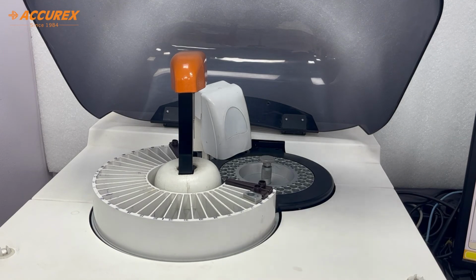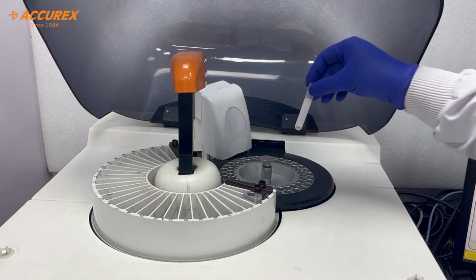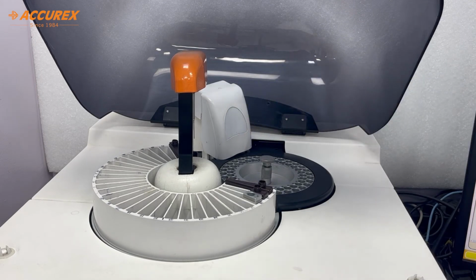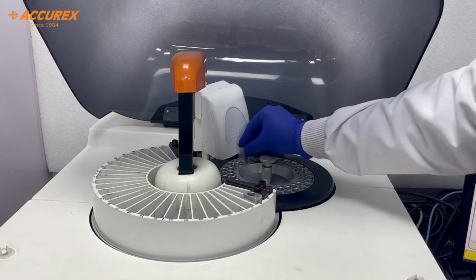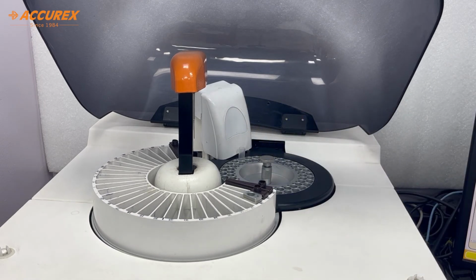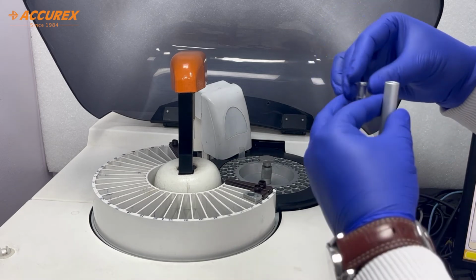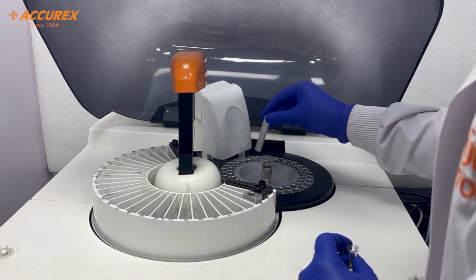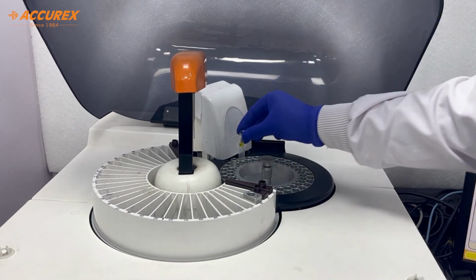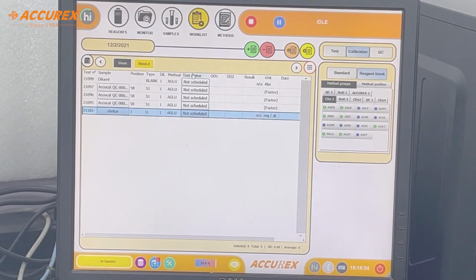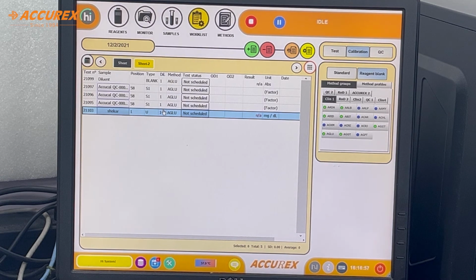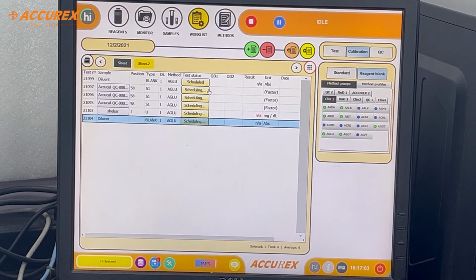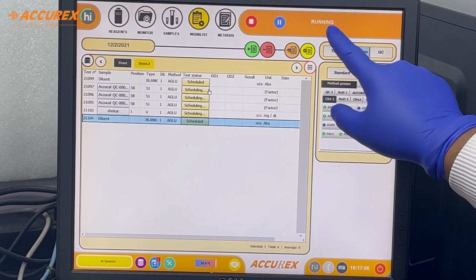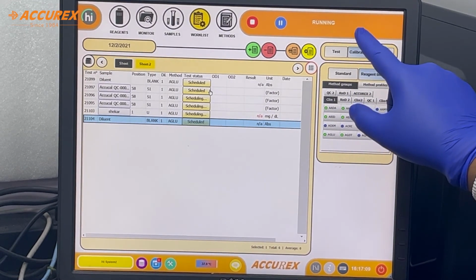Now open the instrument cover. Now you can place the tube where the position has been selected. Currently I have selected the one position, so I will place the tube over here directly. And also we have selected the calibrators. For the calibrator, we have selected the cup mode. So for placing the cup, we need to select the adapter also. So we have to place the adapter on number 58 and place that cup on that. Okay. After placing the calibrator and sample on the position, now click on the start button. So it will start the process. It will show the running time and it will show the timing also when the reaction will get completed.